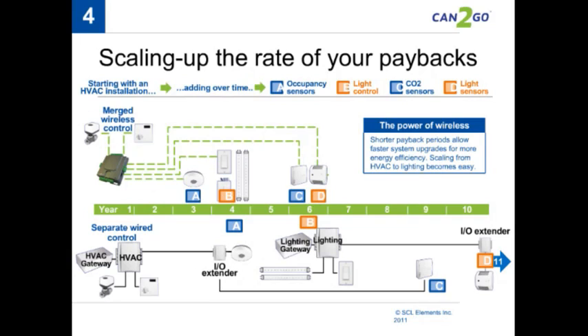Then you need to add another box for lighting controls and gateways, and suddenly you're stuck pulling a lot of wires. There's a lot of downtime associated with all this, and often the ROI just isn't there - so people just don't do it, which is unfortunate. The power of combining all this, and the power of wireless systems, is shorter payback periods, which allow faster system upgrades for more energy efficiency, and scaling from HVAC to lighting or lighting to HVAC becomes a lot easier.